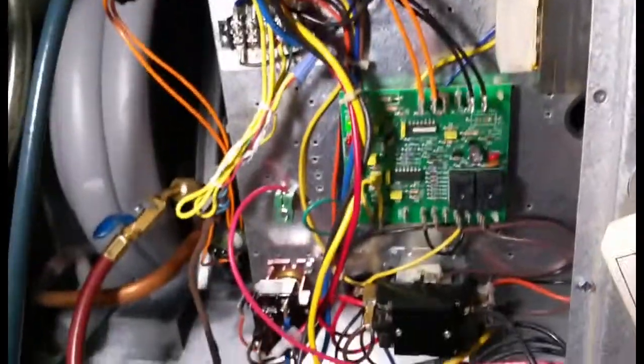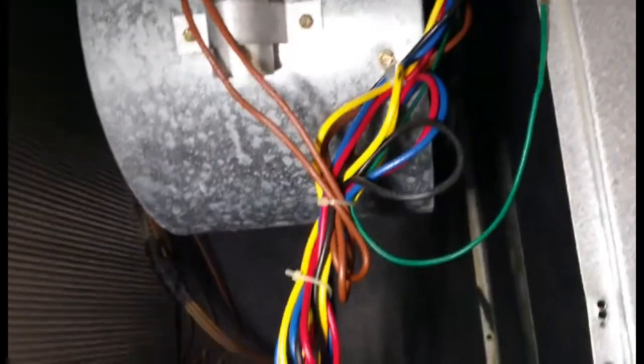And I just want to show you. Yeah. Oh man, jeez, this thing is stuck. Alright. Okay. So you can see how you can tell this, if this was a package unit, you would think that the high port would be the high side and the low would be the low side, but you actually have to follow it. And this port feeds right off of this hot discharge line, and this one right off the suction line. It's hard. It's all tight and cramped up, but I'm just doing regular maintenance, blowing out the drains, new line, algae tabs, and checking the TD pressures, coils, amps.